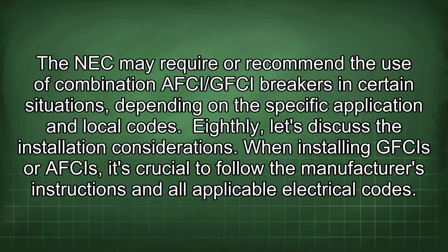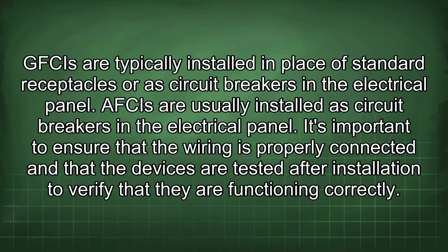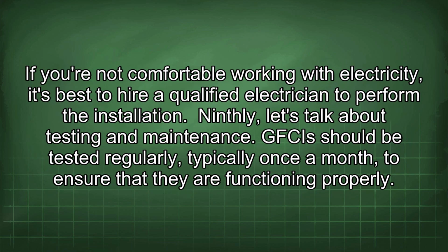Eighthly, let's discuss the installation considerations. When installing GFCIs or AFCIs, it's crucial to follow the manufacturer's instructions and all applicable electrical codes. GFCIs are typically installed in place of standard receptacles or as circuit breakers in the electrical panel. AFCIs are usually installed as circuit breakers in the electrical panel. It's important to ensure that the wiring is properly connected and that the devices are tested after installation to verify that they are functioning correctly. If you're not comfortable working with electricity, it's best to hire a qualified electrician to perform the installation.